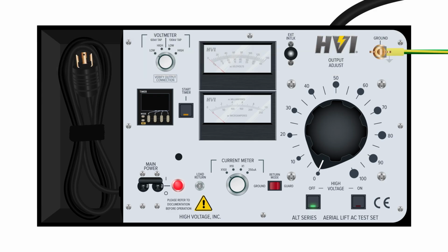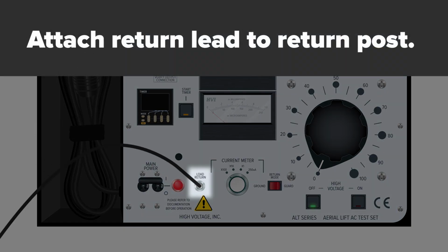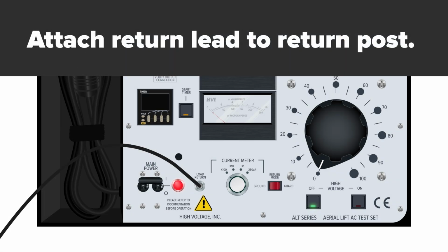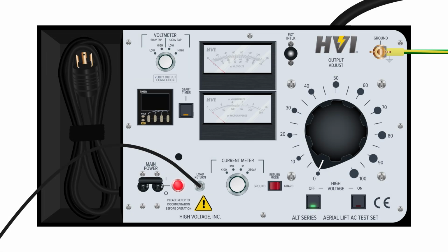Now, connect your load return lead from the DUT to the main control panel. The load return lead also has a black booted alligator clip. Connect it to the low side of the DUT. Return from the low side of the DUT to the load return post by attaching the load return lead to the connection post on the control panel.